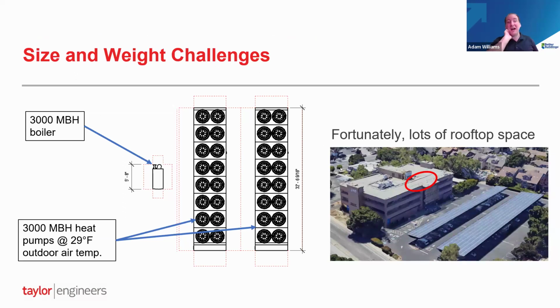Next big issue is size and weight challenges. So here's an example. The box on the left is a 3 million BTU boiler, and the units on the right are 3 million BTUs of heat pumps at 29-degree outside air temp. Significantly larger. These need to be out on the outside, and they take up a lot of space and are heavy. So this is definitely a concern and something we look at on all our buildings: where are they going to go? Because they can't go where the boiler originally went.